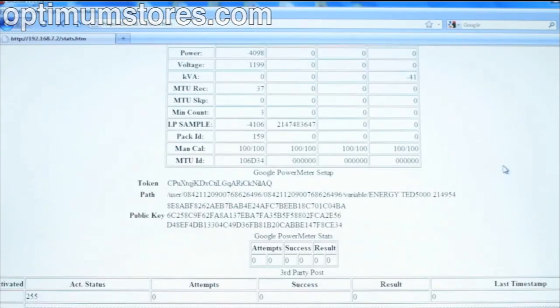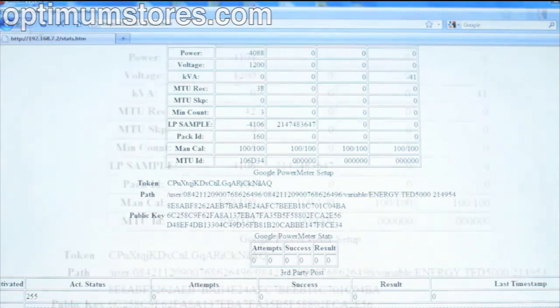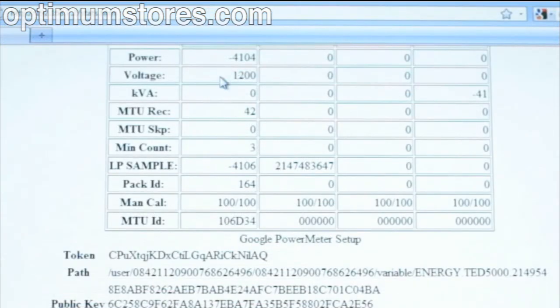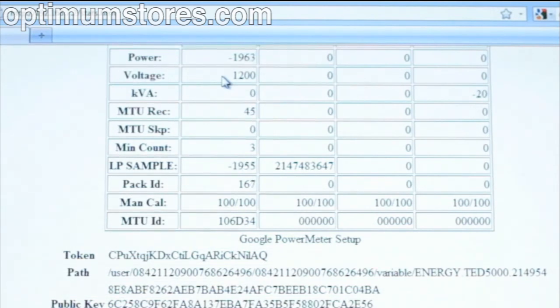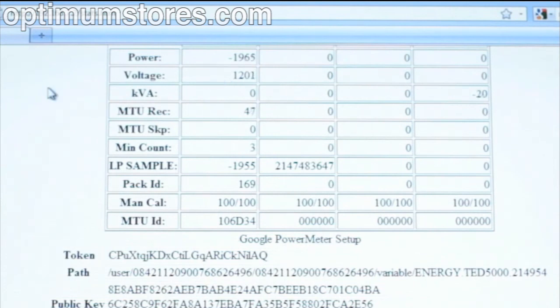If your MTU REC number is counting up but you have no data, look at the MTU voltage. If this is zero, then you likely have the black and red wires of your MTU on the same phase, and you should proceed to our 120 volt MTU connection video. If you have consistent MTU REC and a voltage reading but your kilowatt readings don't appear to be correct, one of your CT clamps in the panel may need to be flipped.